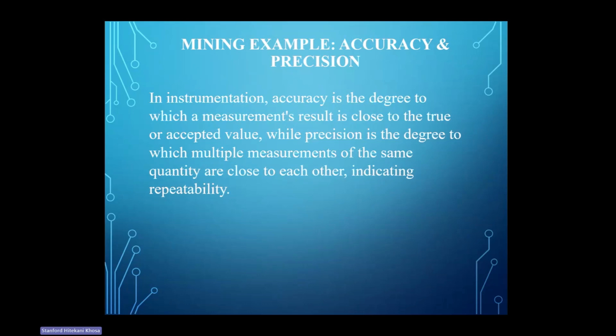So an instrument can be precise but inaccurate, or accurate but not precise. What we need is high quality instruments that are both accurate and precise, yielding repeatable measurements that are close to our actual value. We get this by ensuring that the manufacturers give a recommended calibration period. Most of the instruments that we use, they will say each and every year you must calibrate and have a calibration certificate.